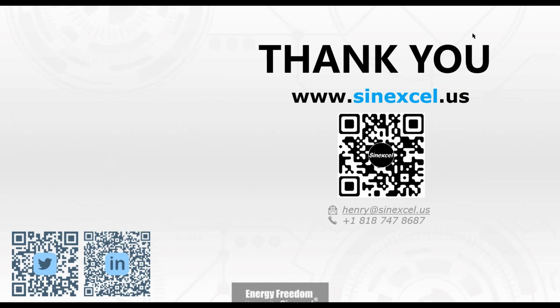Sure. Okay, so basically in terms of battery, to be able to be grid forming in a safe environment, which I guess is what we all want, first it needs the BSS, we need to make sure that we have the capability to be grid forming. And second, the capacity of this battery is higher than the maximum loads, meaning that no matter the loads we are having, this battery will be able to supply them. Otherwise the loads are higher than the battery, so we will create an instability, and that's not a good solution.